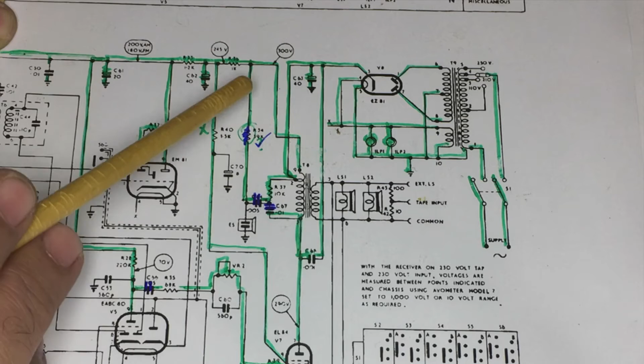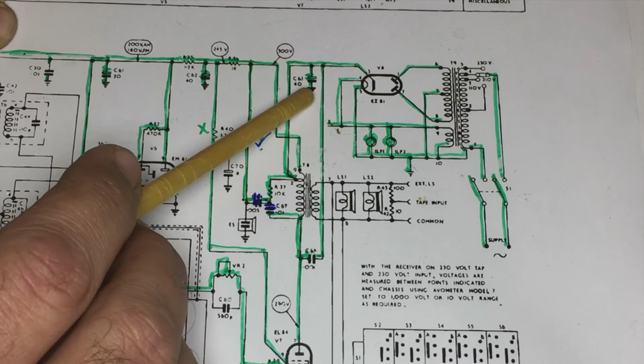So I dropped the voltage down and just reformed them slowly, bringing up the voltage. After about a couple of hours on each section, I've now got these leakages to acceptable levels of about 400 microamps. So that's fine for this value of capacitor and this operating voltage.